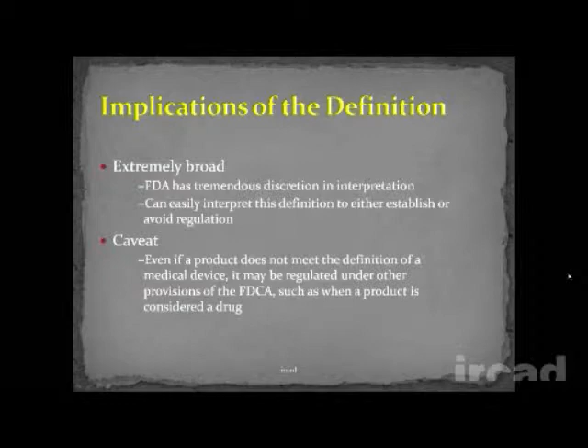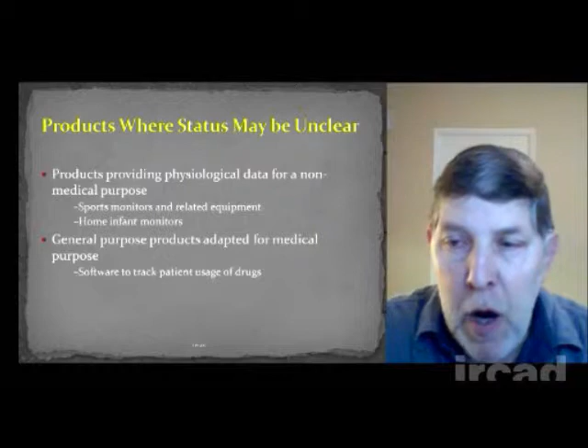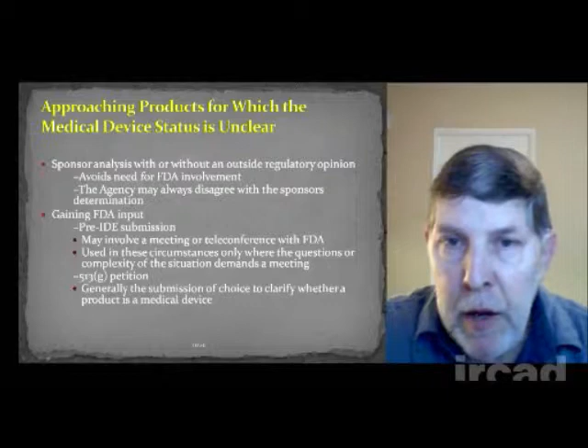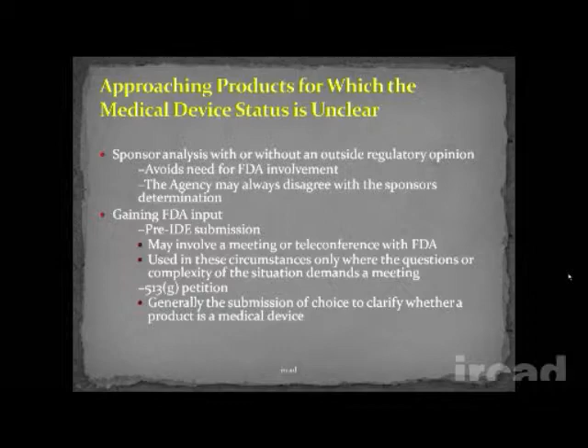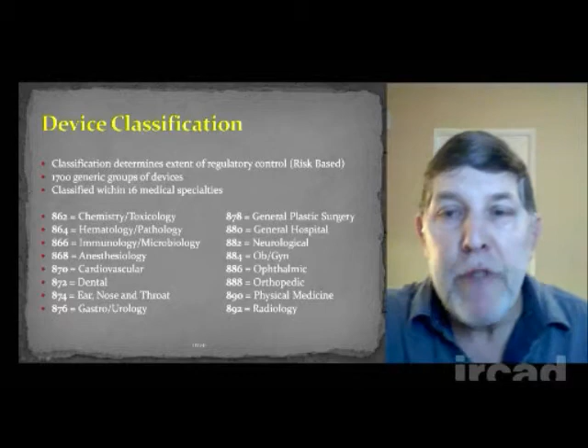So, as an example here, products where it's not entirely clear that a product is a medical device, such as a sports monitor or home infant monitors, general purpose products. It's not clear that those are medical devices. And in the case where it's not clear if a product is a medical device or not, then there's a couple options. One is that you can talk to FDA and seek a regulatory opinion as to whether a product is a medical device. And FDA has the right to disagree with a sponsor's determination. And you can also request a meeting with the FDA or teleconference to discuss the status of a product.